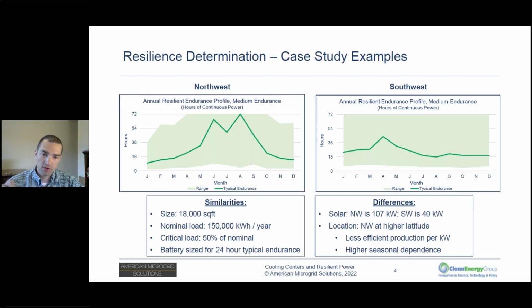For this part of the analysis, we assumed both would shut down half the building during an outage, operating at half capacity, and wanted 24 hours of endurance as a typical result over the year — so the battery is sized for that. In both cases, the worst case performance tailored to battery size is proportional to that battery size. The southwest facility has a slightly larger battery, so its worst case performance each month is usually slightly better than the northwest facility's.